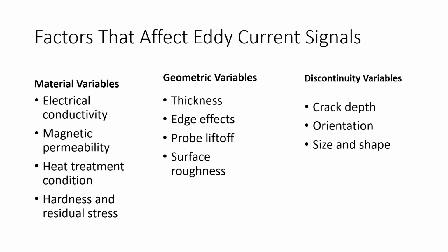And then you've got geometric variables here like thickness, edge effects, probe liftoff, surface roughness. How rough is the surface? Is it a machined surface or is it something that's just a jagged, craggy mess? That's going to affect our signal. And then discontinuity variables. When we're running our eddy current probe across the material, discontinuity variables are also going to affect this. And that would be things like crack depth, orientation, and the size and shape of our discontinuity. All of these are factors that are going to affect that eddy current signal.